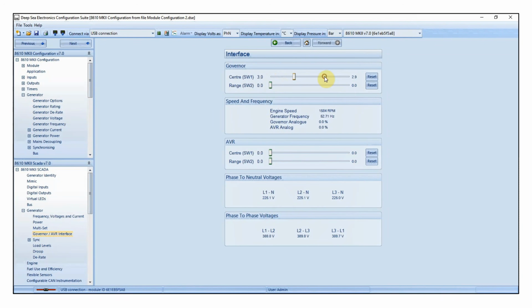You can see on the example here, I've made a lot of change and nothing's happened. This could be due to how the governor works, could also be due to a wiring problem. What we advise you do is keep going all the way to the end until you see a change. Like, for example, I've seen now. It is very important to note, however, in this example, that as I increase switch 1, the frequency is going down. Normally, as you increase switch 1, the frequency would go up. Now, this is not necessarily a problem, and I'll tell you how we combat this later, because I want to show you what would happen if we don't fix it to start with.